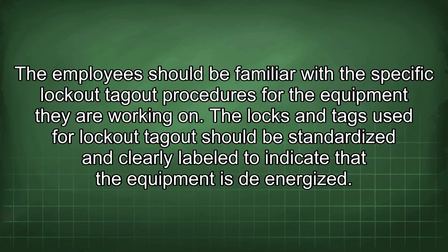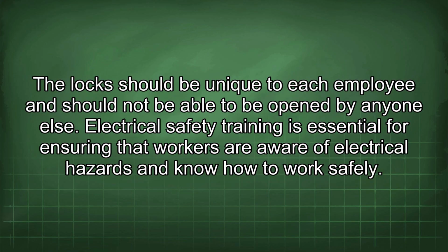The locks and tags used for lockout-tagout should be standardized and clearly labeled to indicate that the equipment is de-energized. The lock should be unique to each employee and should not be able to be opened by anyone else.